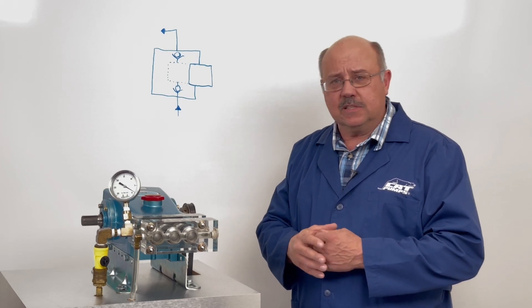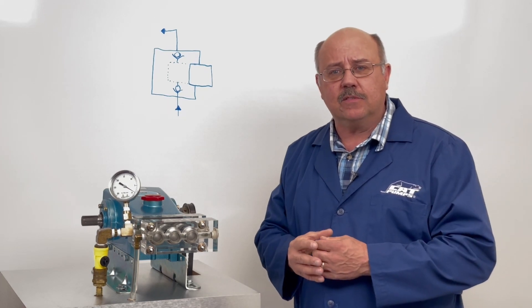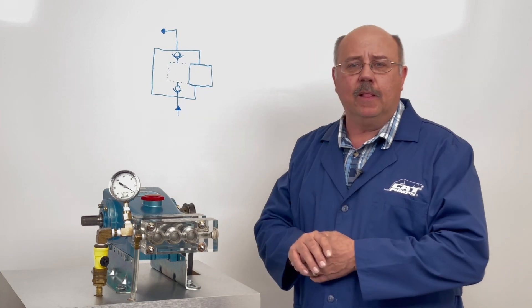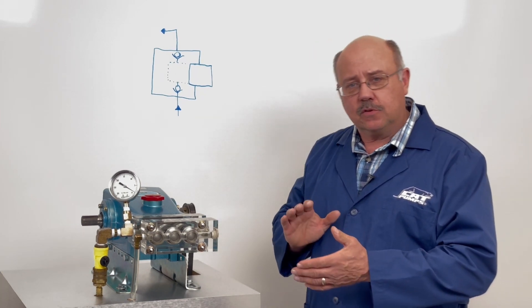And that's what cavitation is, is this expanding of that liquid into a gas phase, and then it re-collapses on the forward stroke as you start to build pressure.